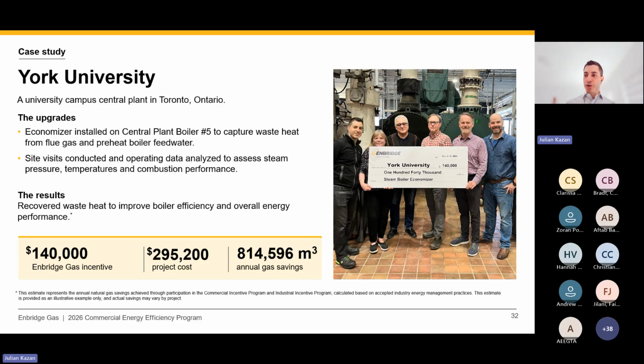We said, okay, if you drop the flue temperature by 120 to 150 degrees Fahrenheit and put an economizer in there to feed that heat into the feed water, what savings could you expect? We came up with a business case and an incentive, and the project was essentially a slam dunk: they're saving 800,000 cubic meters per year with the economizer. It only cost them barely 300,000, and we covered almost 50% of the cost with an incentive. So this is the kind of scale we can go up to with a custom incentive program—it's not just limited to controls projects or quick turnaround projects. We're really willing to look at any kind of gas savings measure and try to provide an incentive and an energy savings calculation for it.